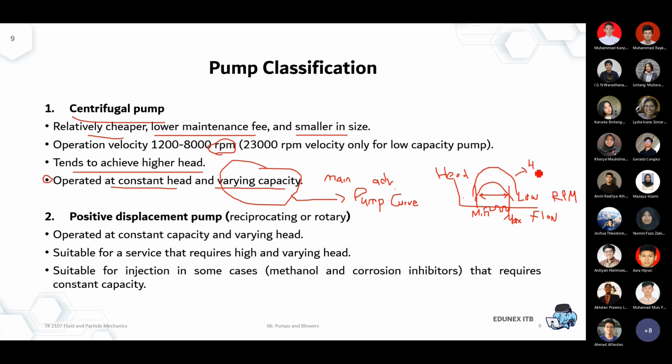So during some very specific requirement, when we need more pressure differential than the normal one, we can simply increase the RPM of the impeller, and then it will allow us to get a high differential. Okay, a higher head means a higher pressure differential. So again, it's very flexible. That's a good word to put it. The advantage of a centrifugal pump: we have a range of the flow rate, and we could also play around with the range of the head generated by changing the RPM of the centrifugal.